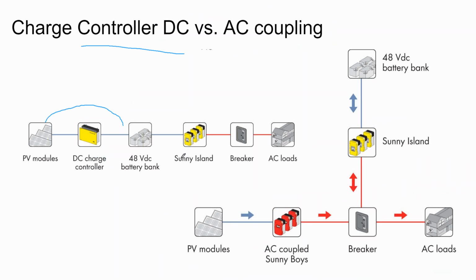And so on one of my designs, we needed to upgrade our breakers. I made a design error. This is rated for an 80 amp output, and my design error was that I ordered the 80 amp breaker rather than the slightly oversized 100 amp breaker. And we were getting into spring, and our array was at full power. And whenever the home would draw the full rated power out of the inverter, the charge controller was delivering its full rated power to the system so that we wouldn't have to use the batteries. And so that meant we got up to the 80 amp output, and the breaker kept tripping. So I was like, okay, well, I actually need to fix my design mistake. I need to go and get the 100 amp breaker instead of the 80 amp breaker.